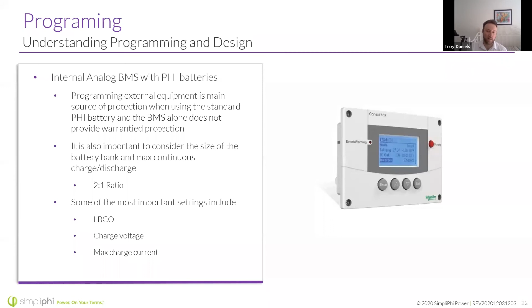Some of the most important settings when programming one of our batteries with this BMS: looking at the low battery cutout. How low do you want a battery to go? For instance, if it's a 48 volt battery, 48.0 is actually the 100% depth of discharge, as low as we want to go. Charge voltage, meaning the high end voltage, is also important, since the BMS isn't telling the system what to do. And max charge current is really important as well.